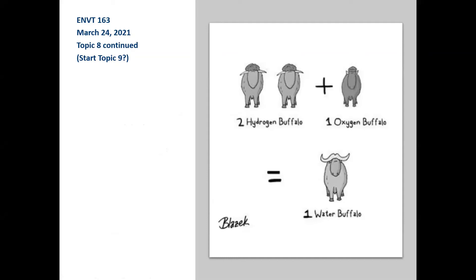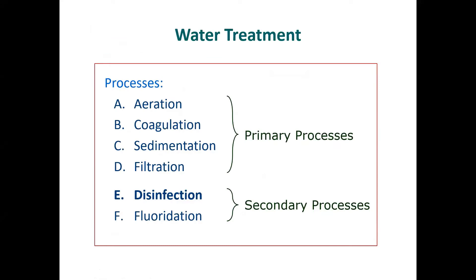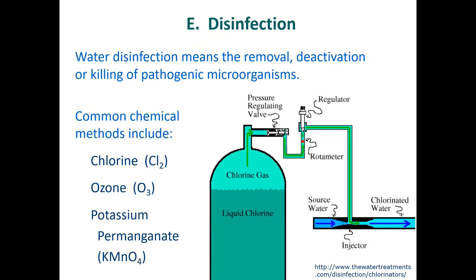We were talking about water processing, and this is where we finished off talking about disinfection. For disinfection, we talked about chlorination, and I mentioned that sometimes we don't necessarily always use chlorine — sometimes we use chloramines. They're a little bit more persistent, so depending on your distribution system, in the case of Fort McMurray where we're trucking water around, chlorine will stay in the water for about 24 to 48 hours. If you're expecting it to be in a system longer than that, chloramines are a good fit.